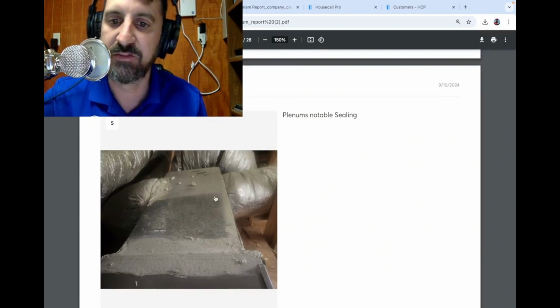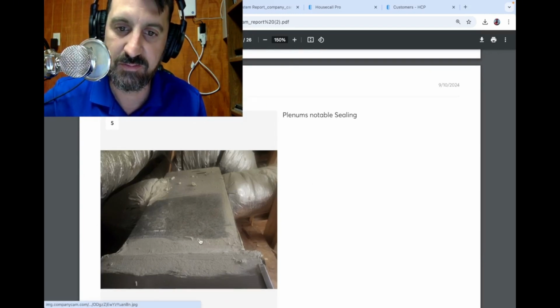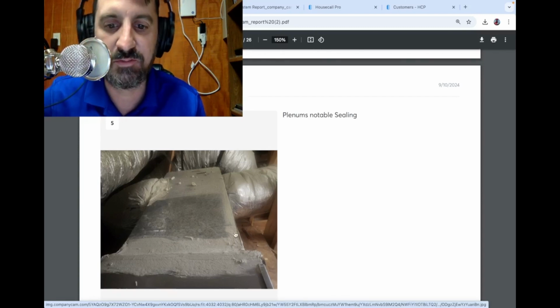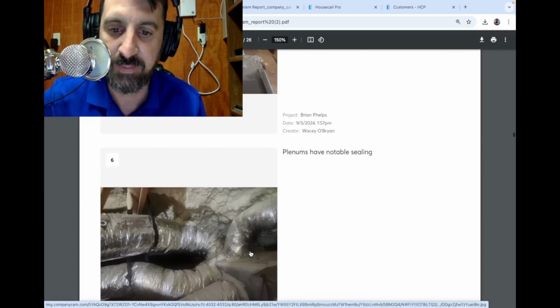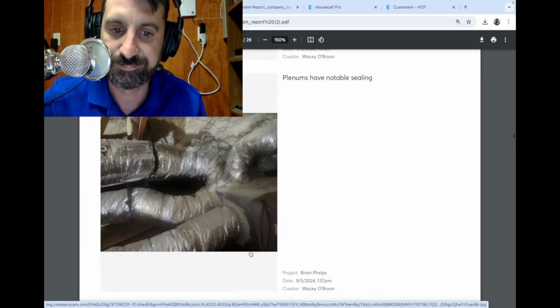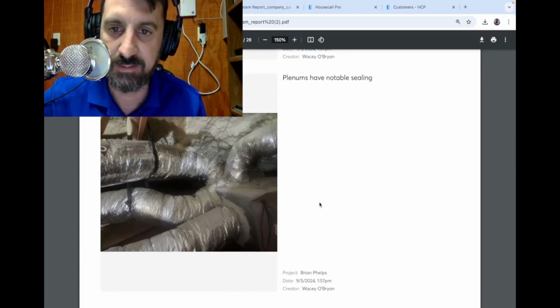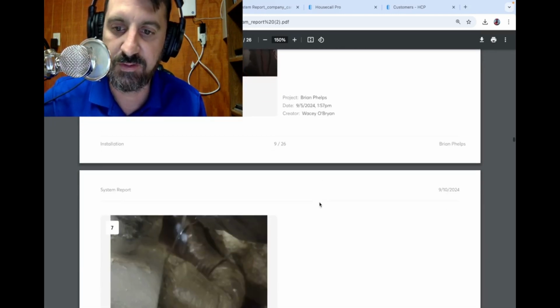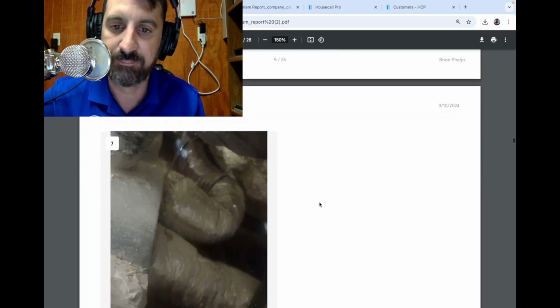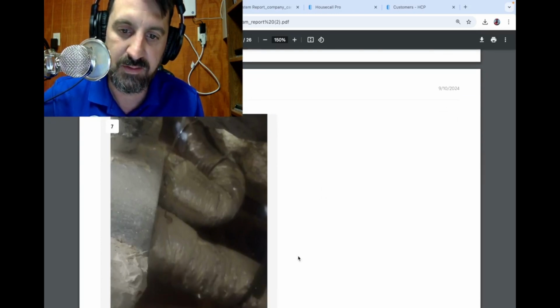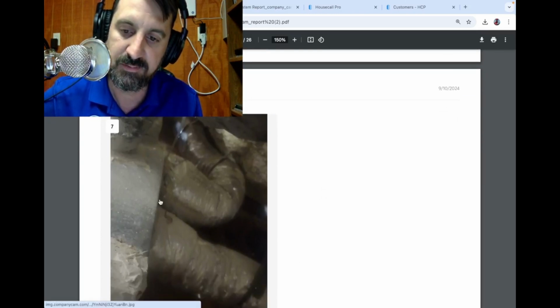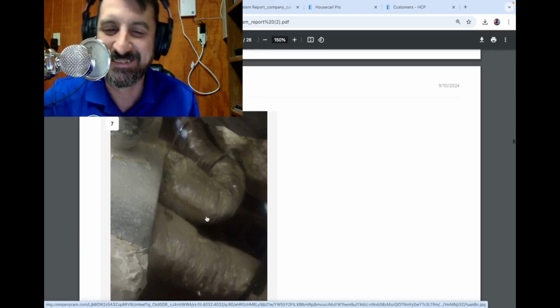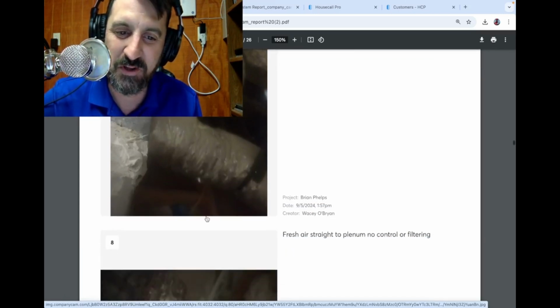The plenums have been sealed really good. You can see they painted them up good. They made sure that air was delivering properly. Again, another picture of the ceiling. This is coming off the back of the unit. They've got hangers. Ductwork for delivery purposes wasn't done terrible.